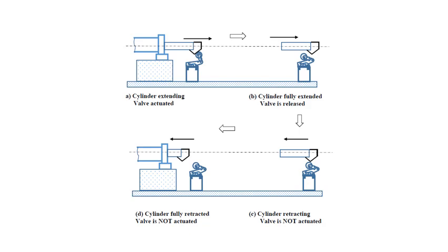Here, above the cylinder rod, in a wedge type of position, you want to get the actuation signal. While the cylinder is moving forward, it will actuate. But in the same case, while retracting back, it will only bend, it won't generate the signal. See here how much it is pressed, but here how much it is, right? It won't push the plunger, but the idler roller itself bends with respect to the given hinge, so it won't generate the return signal.